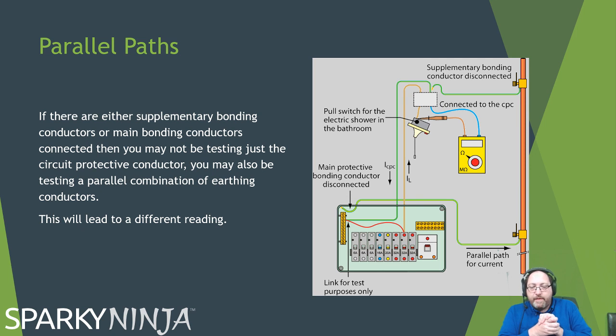They're a nightmare. In twin and earth insulated systems, they're quite easy to control. In larger complex systems with metal conduits, metal trays, and you find yourself getting low readings to earth, it's likely that the parallels are having an effect, but you need to be able to take account for that instead of just going, must be a parallel. You make sure you understand why they're there.